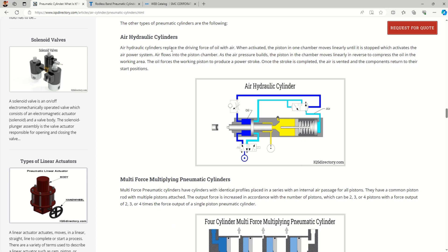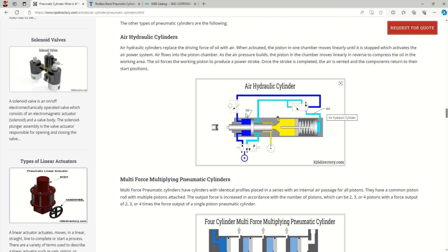Air hydraulic cylinders use both air and oil, and are also called pneumo-hydraulic or hydro-pneumatic cylinders. They are used when high forces are needed within a small size. For example, in a 200 mm stroke application, the first 180 mm is a fast-forward stroke using air, and in the last 20 mm oil comes into play to deliver the main power stroke. This is a good solution instead of using fully hydraulic cylinders, which have higher maintenance costs.